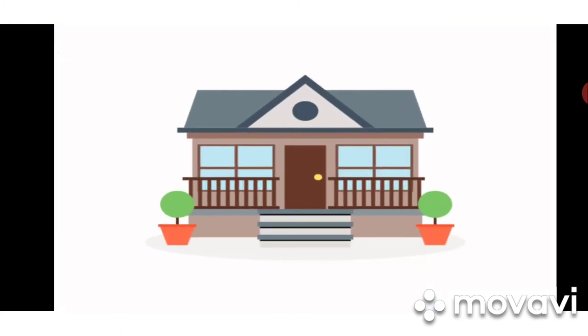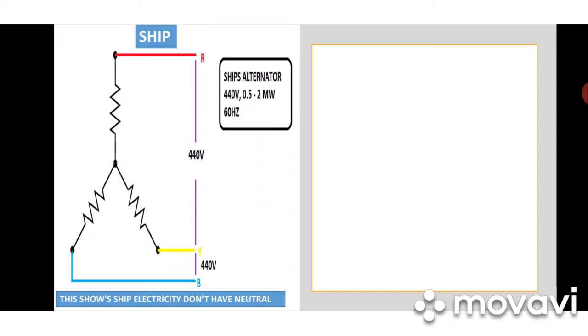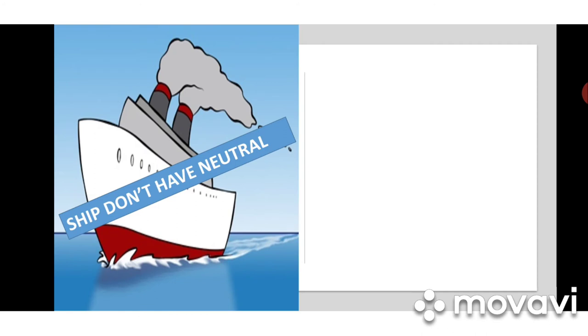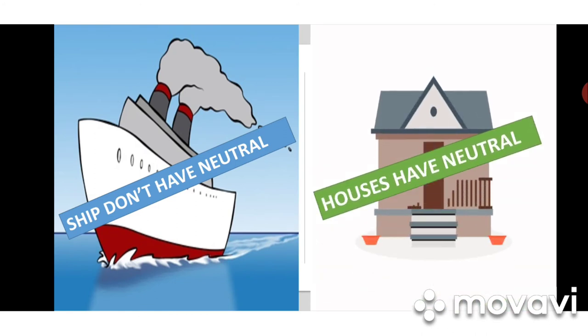Now we will see the difference between ship electricity and home electricity. In a ship, we don't have a neutral — that is a major difference. In your home socket, we have phase and neutral. But in a ship there is no neutral, so we use phase and phase. This is shown in the ship alternator diagram — no neutral is taken from the generator. In the power plant, they take a neutral point from the generator.